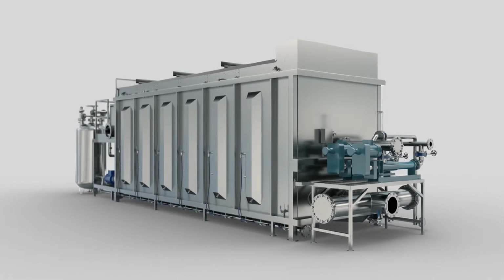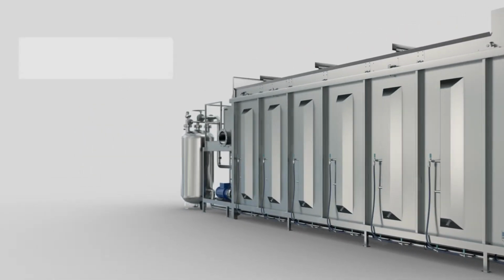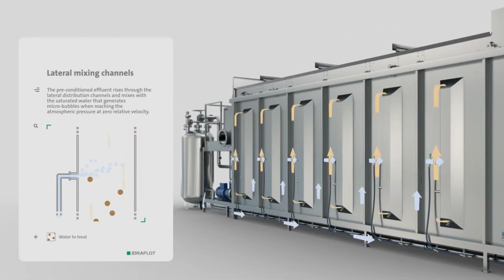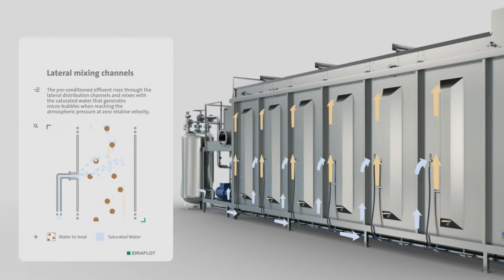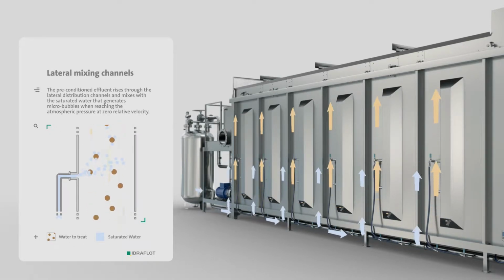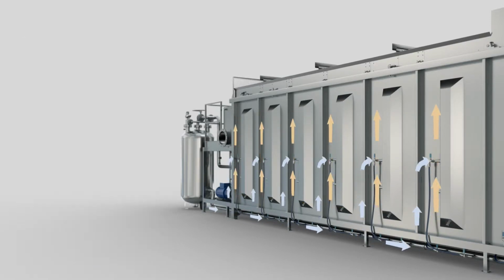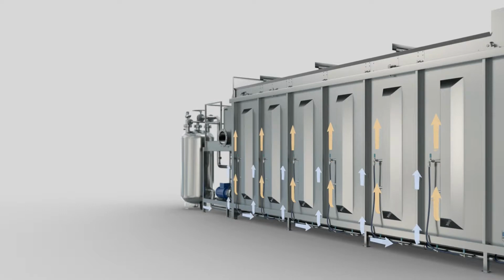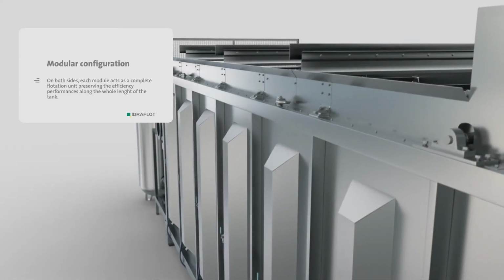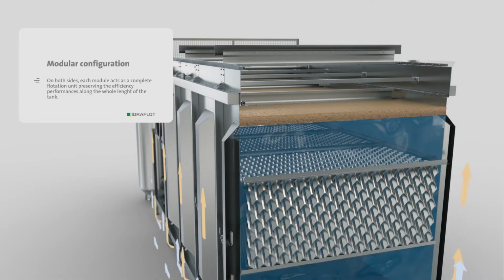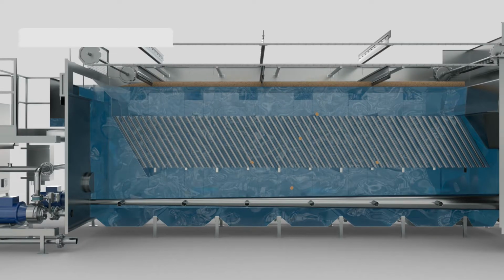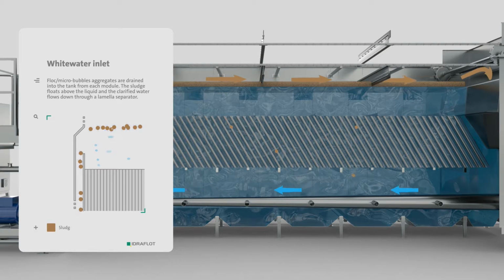The flow, divided into the lateral mixing channels present on the outside of each flotation module, is mixed with saturated water. The sharp drop in pressure develops microbubbles which adhere to the flocks. Along the whole length of the tank, each module acts as a self-complete flotation unit, increasing performance and reducing chemicals consumption.